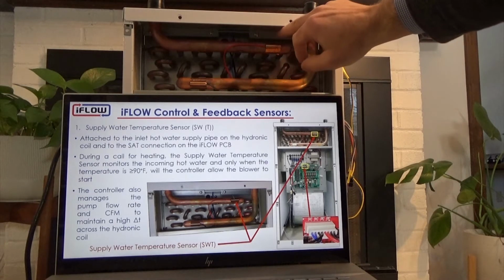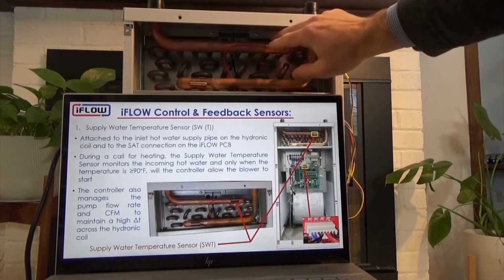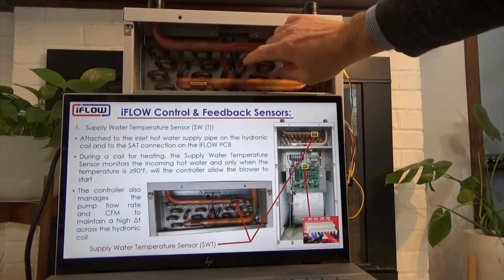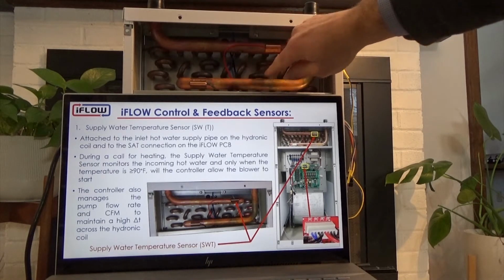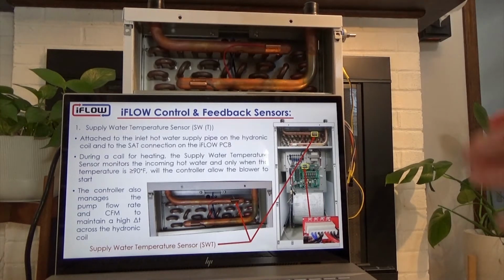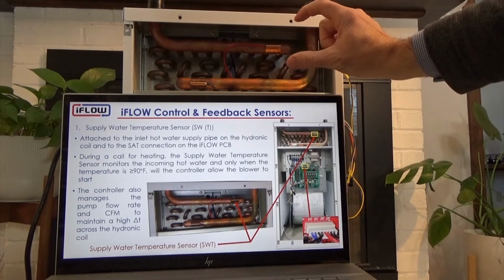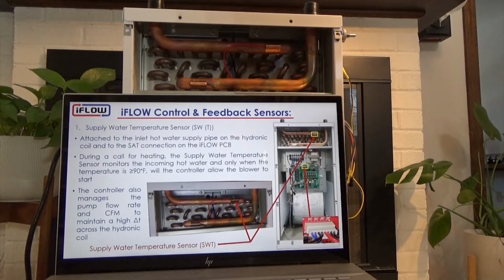Then the difference between the input and the output, the supply water temperature and the return water temperature, gives us our delta T. And with that we can look at adjusting either the flow rate or the CFM rate to maximize the delta T across the coil to ensure you're getting great efficiency.